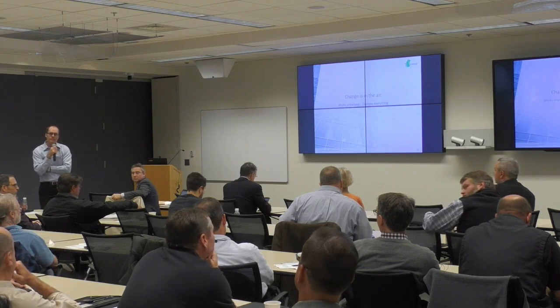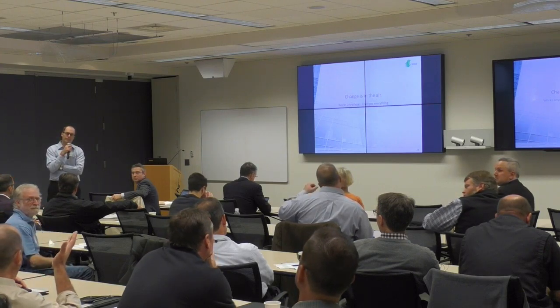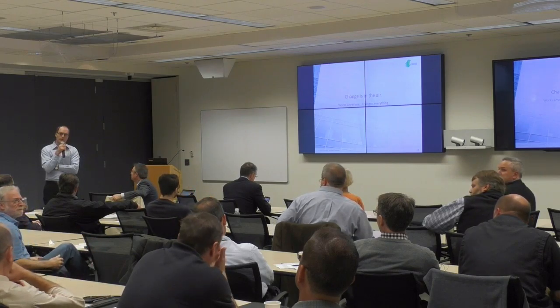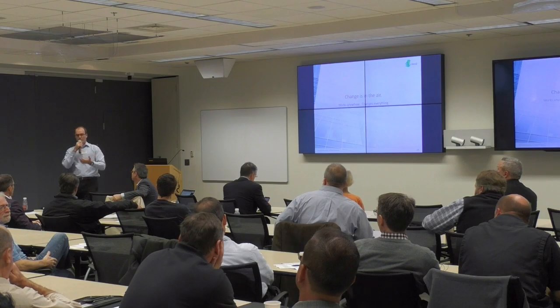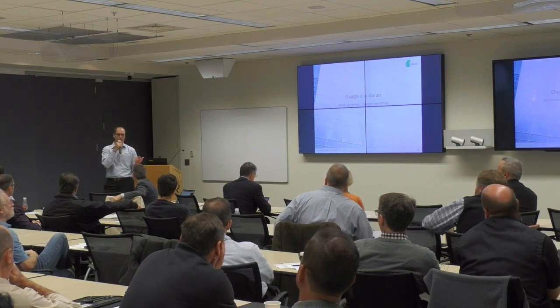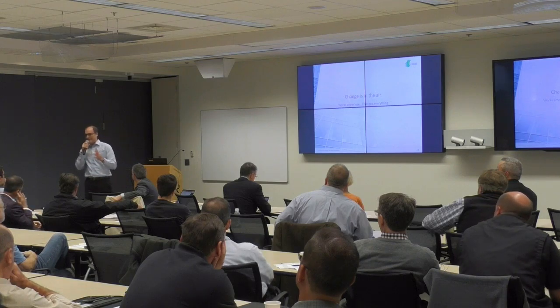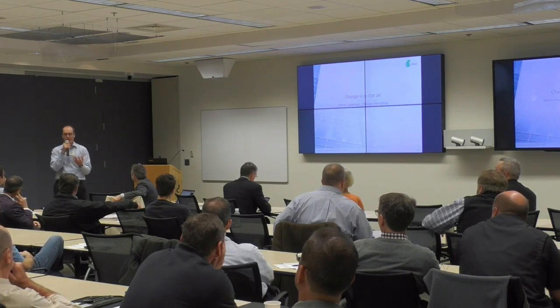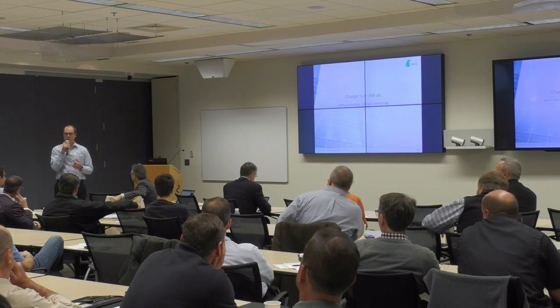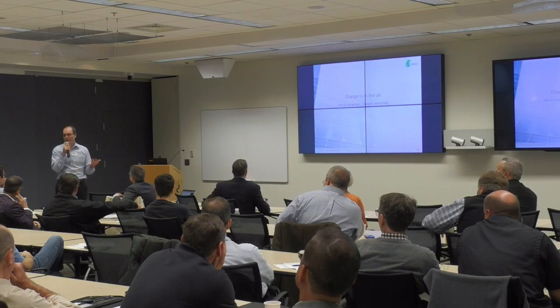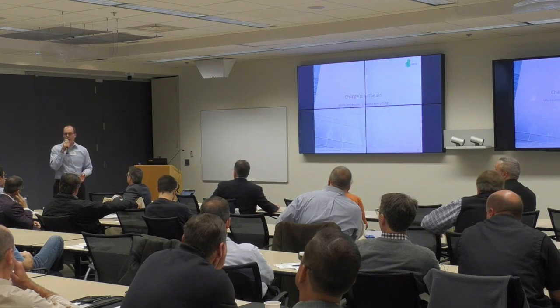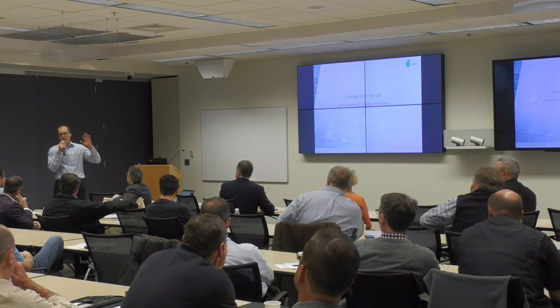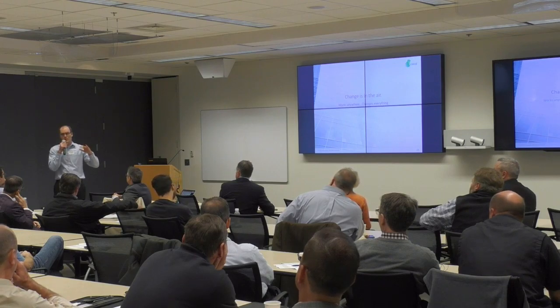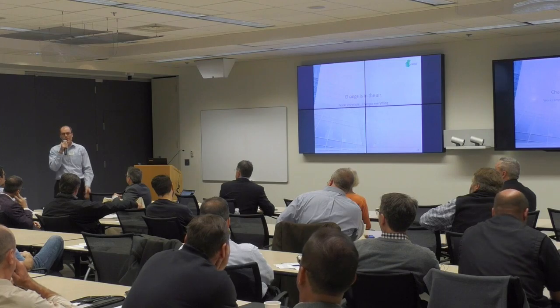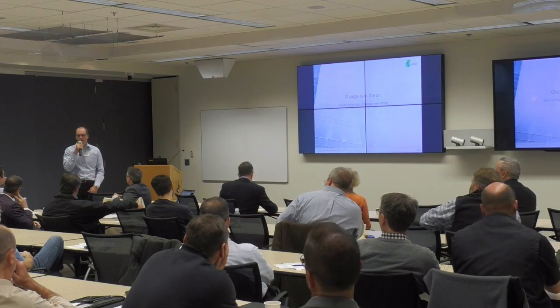How do you size these? If you have an air handler with return air, 30,000 CFM, what percentage of the CFM are you targeting? There's a formula in the ASHRAE spec, and so we use that. I hate to give rules of thumb, but I will, because you gotta have them. For like an office building, we usually hook one of these units up to a 20,000 or 30,000 CFM air handler. So we have a high rise with 38 floors, and there's one unit per floor, because the high rise is around 25,000 square feet a floor.